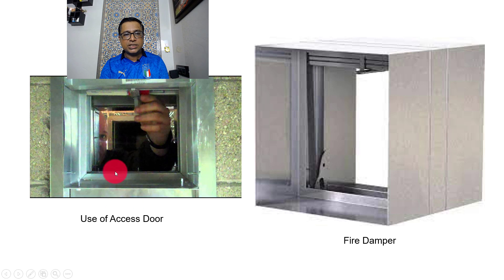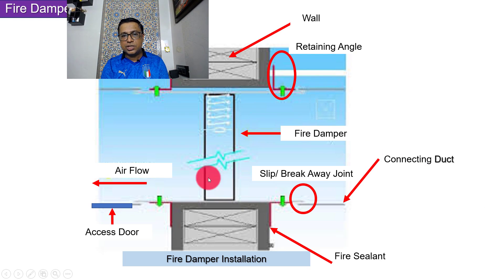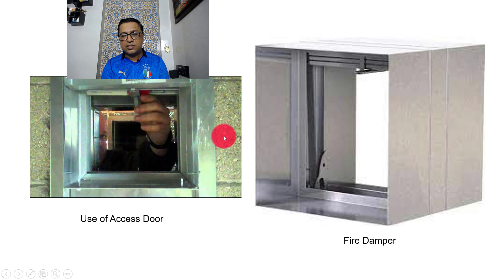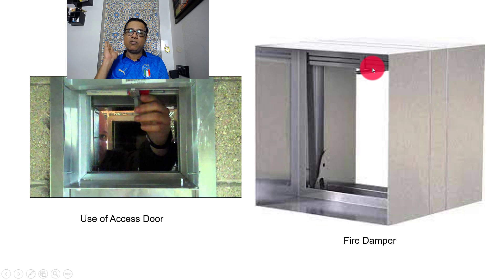From the access door, you can access the fusible link if there is an issue. This is a real fire damper — this is the head, and this is the curtain which goes inside. This is the fusible link, this is the sleeve, and the fire damper is inside. This has to be aligned with the firewall — that is very critical.